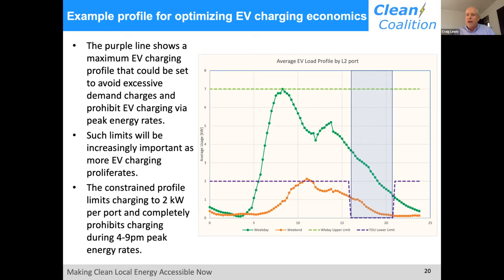This chart shows a typical commercial or even a community or town-center type setting. The green line is the weekday charging profile, the average on a given charging port. The brown curve on the bottom is weekend utilization. The purple line shows that, for economic reasons, you may not want charging fully available at full speed all the time, so you can apply whatever charging profile you want to optimize economics. At the same time, by designing it behind the meter, you can deliver energy through your solar microgrid when the broader grid is down, keeping emergency vehicles charged. And when you have plenty of solar availability, you can make it available to the wider community so they can keep their electric vehicles charged too.